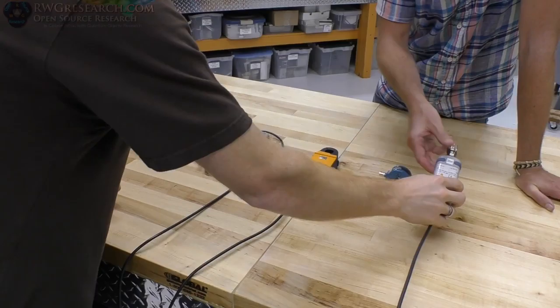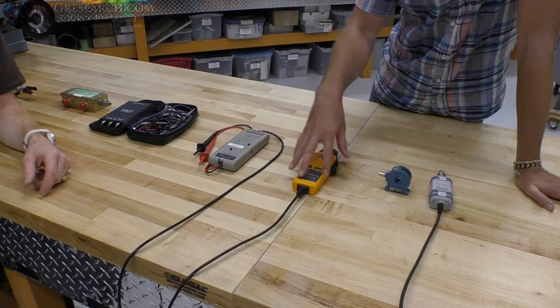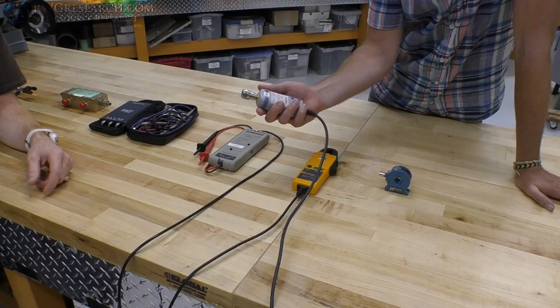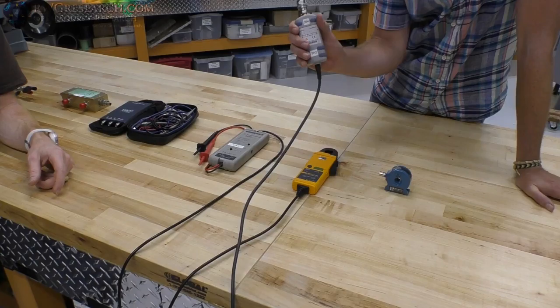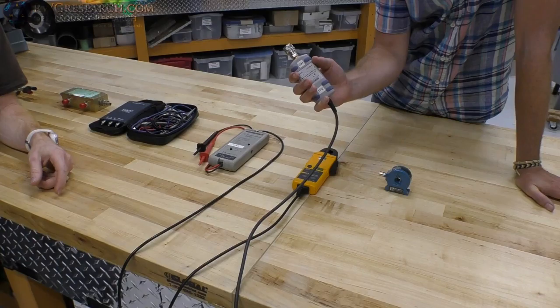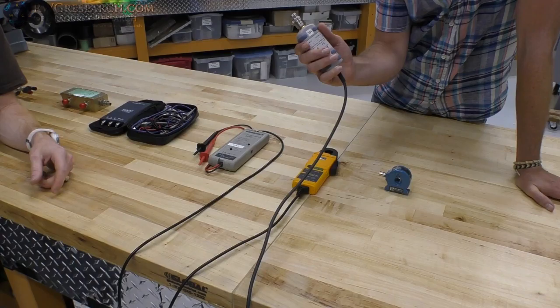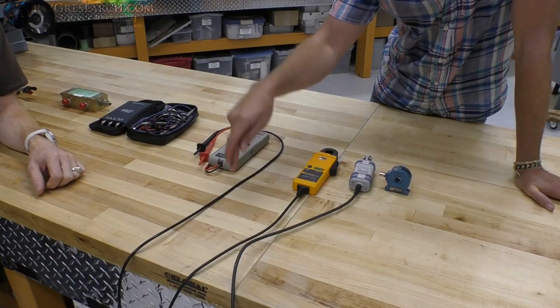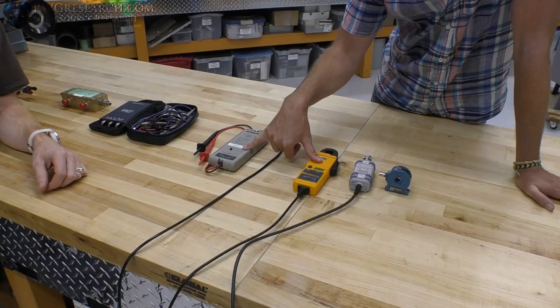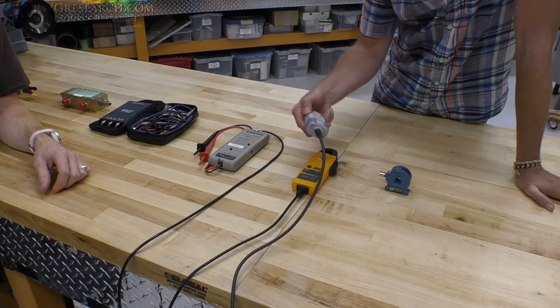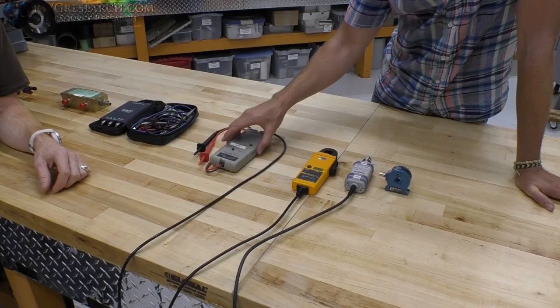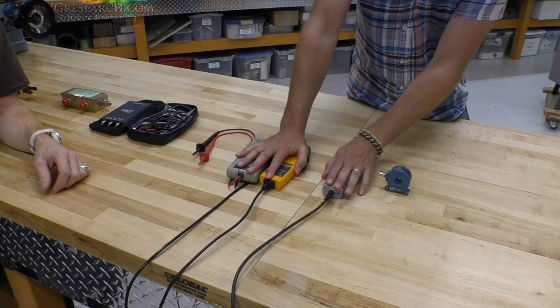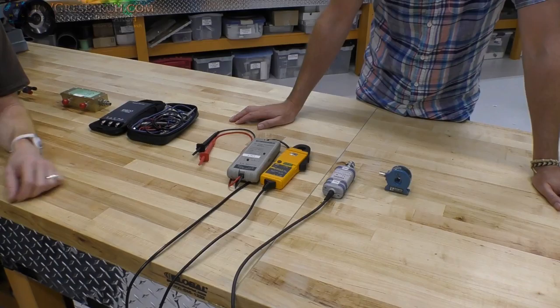This is an unbelievable piece of equipment for calibration because what you can do is you can make measurements of voltage and current going to a resistor. In this case, the resistor is inside the thermal power probe, and you'll be able to calculate the power. Let's say it's 100 milliwatts of power, which is shown on your thermal power probe, which goes to a piece of software on a PC. You're dissipating 100 milliwatts of power into that resistor. You know that. Now if your voltage and your current meters on your oscilloscope are showing you that you've got 0 degrees of phase difference and you're calculating 100 milliwatts of power, you're good. You're good to go. If you can do that across the full frequency range, I mean this probe here will go from DC to 18 gigahertz. If you can absolutely know that these two, voltage and current, are giving you the same as your thermal power probe, you're in business. You know that you're going to be creating some good quality power measurements.